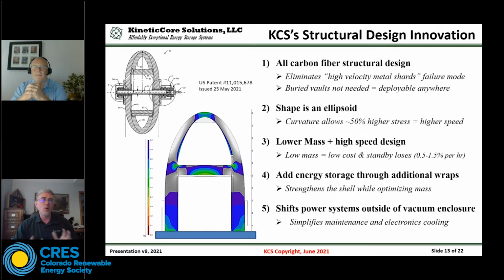The shape, as I mentioned, is an ellipsoid, and this curvature allows us to handle up to 50% higher stress. That translates to being able to go 50% faster speed-wise than our counterparts in traditional flywheels. This low mass, high-speed design, since mass is directly related to cost, means low mass results in a low-cost system. Also, because we are low mass, our standby losses are significantly lower. Therefore, we can do a standby of 8 hours, 16 hours, and still have useful power to provide if the customer requires that capability.